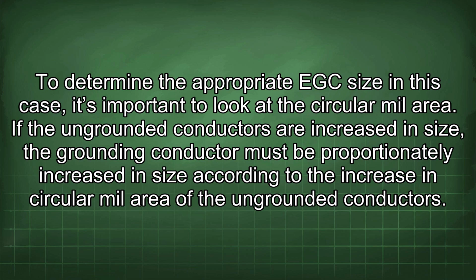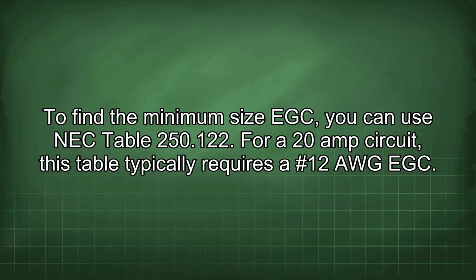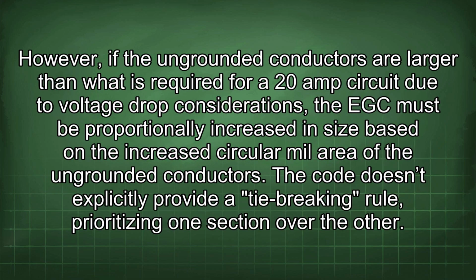To determine the appropriate EGC size in this case, it's important to look at the circular mil area. If the ungrounded conductors are increased in size, the grounding conductor must be proportionately increased in size according to the increase in circular mil area of the ungrounded conductors. To find the minimum size EGC, you can use NEC Table 250.122. For a 20 amp circuit, this table typically requires a #12 AWG EGC. However, if the ungrounded conductors are larger than what is required for a 20 amp circuit due to voltage drop considerations, the EGC must be proportionally increased in size based on the increased circular mil area of the ungrounded conductors.